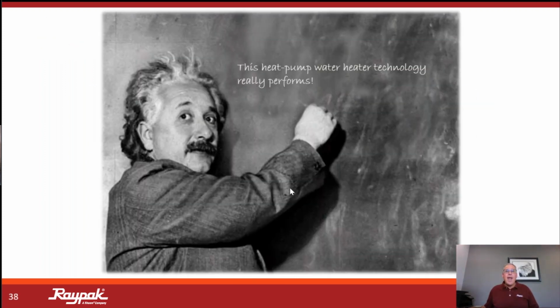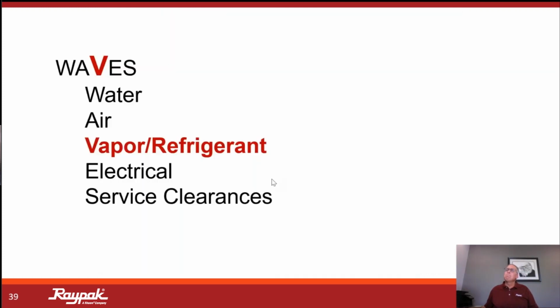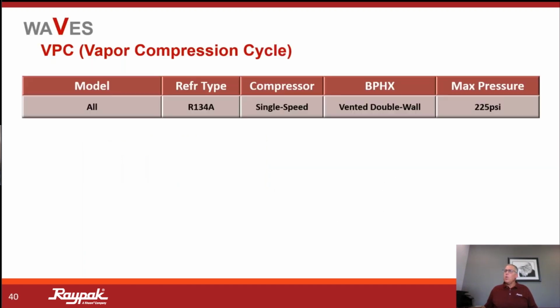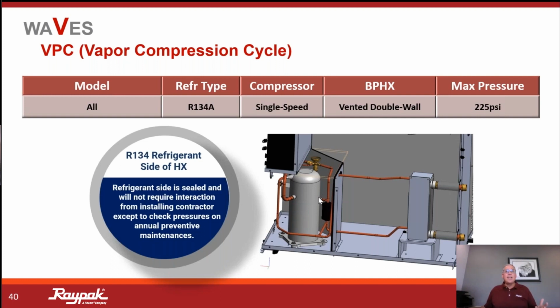So again, if you look at air, you understand that really is driving that efficiency and the performance, and we can do some really good things. Now, again, as we said earlier, on the vapor compression cycle, the refrigerant, we are using R134, and it is a single speed compressor. A lot of people in the industry are using multi-speed compressors or variable speed compressors. The brazed plate heat exchanger is a vented double wall, but this is all self-contained. This is not going to require us to interact on the installation side because it is sealed for us. So it makes this side of it fairly quick and simple.